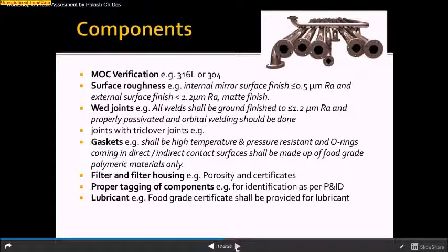Even whether your gaskets are compatible with acid or alkaline needs to be checked. Next is filter and housing. Porosity and certificate should be there for filter and housing. Proper tagging is also required. Proper tagging of components is required for identification. Once you do your maintenance, if there is a tag, you can easily identify it from your P&ID.